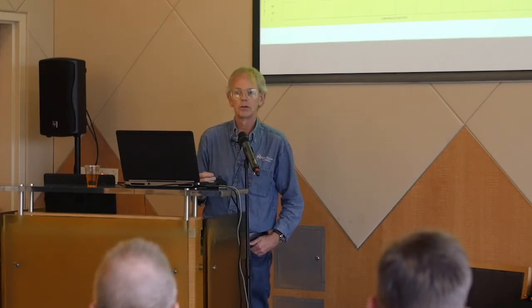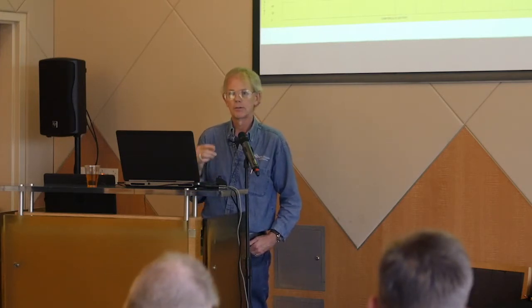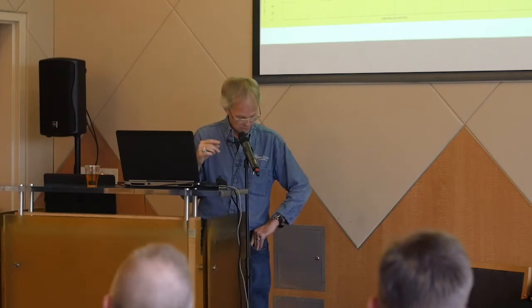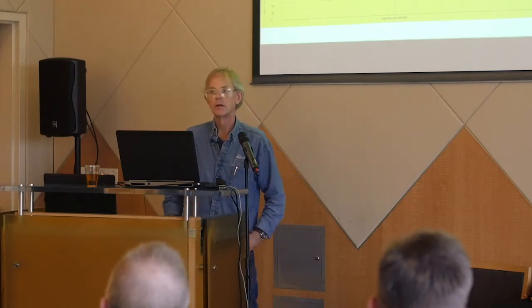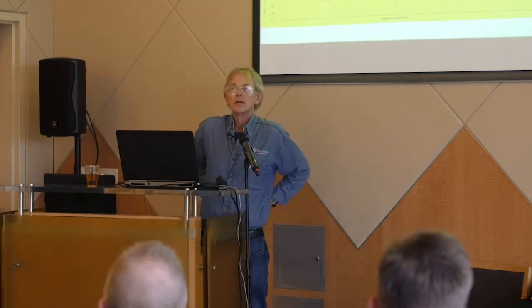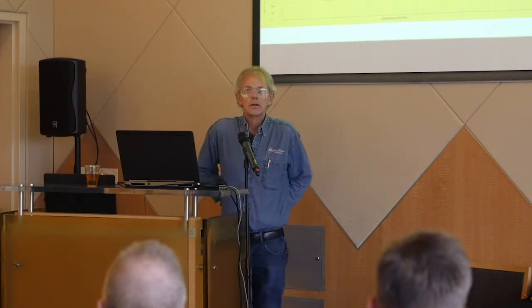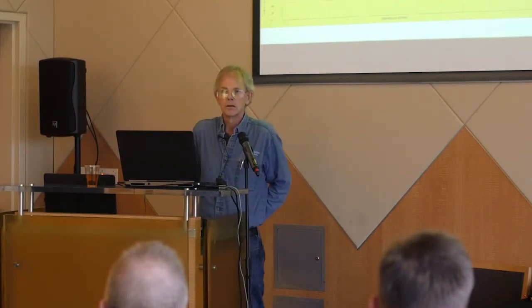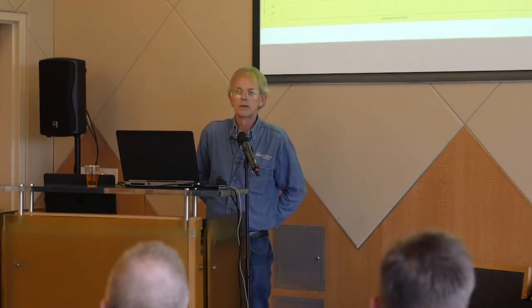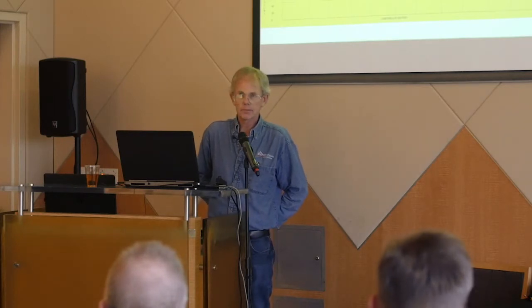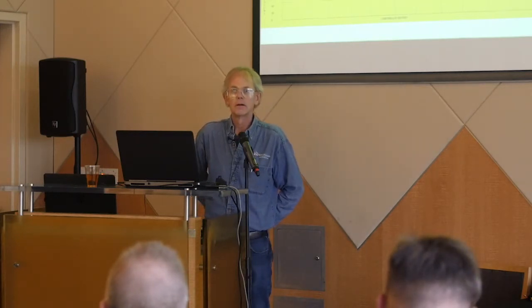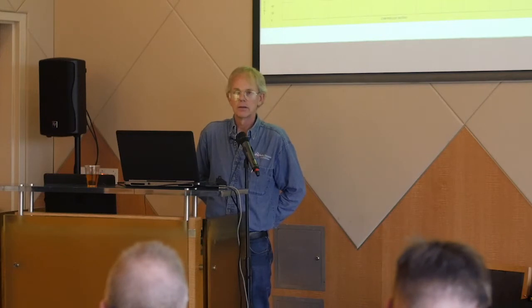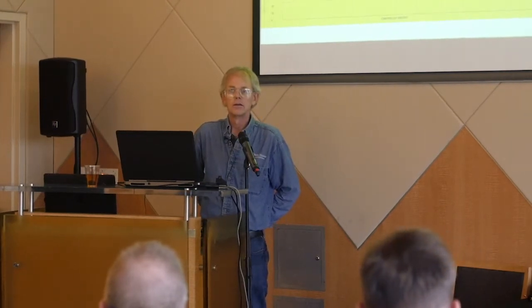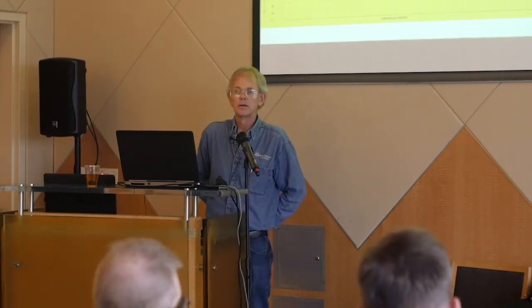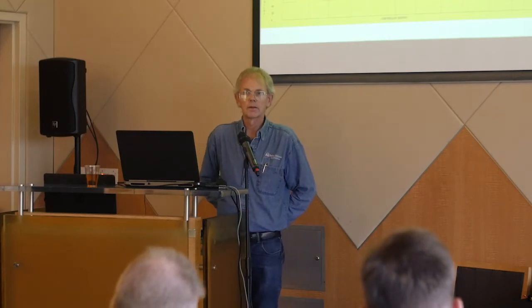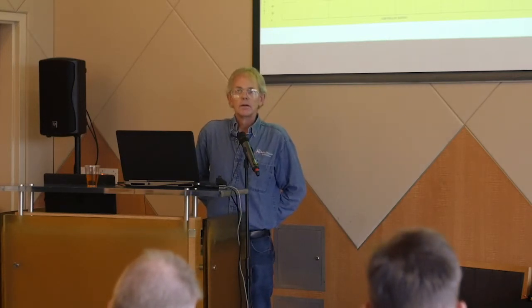So, are there different theories for PID tuning? For example, I noticed when I work with Johnson Controls and you're doing PI tuning, the proportional band may be, let's say, a large number like 100, right? Compared to some other PI tuning or PID tuning where the proportional band maximum is 25 or 30.